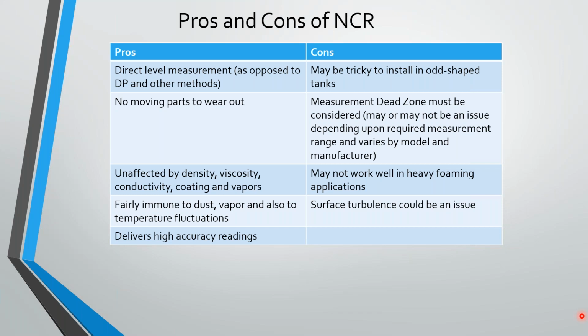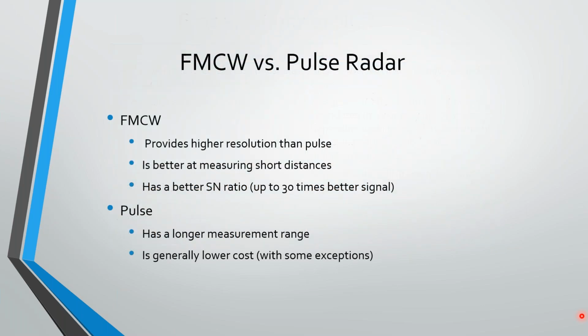What are the cons? Well, if you've got an odd shaped tank, it may get a little bit tricky to install a non-contact radar. I'm not saying it can't be done, but you're going to spend a little bit more time. You might have to play a few tricks. You might have to use an angled flange to aim the device so it's not aiming straight down, etc. We do have to consider the dead zone. Okay, may or may not be an issue. May not work well in heavy foaming applications, and surface turbulence could be an issue, again, depending on which frequency device we're using. So, FMCW versus pulse radar, okay?